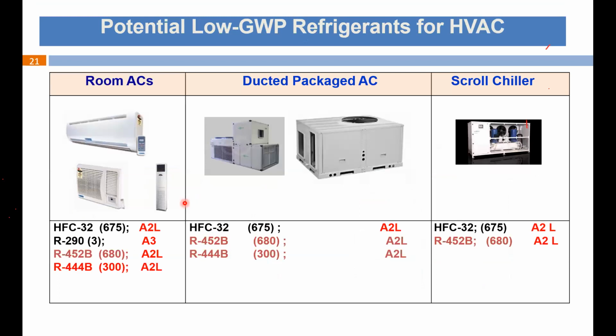Coming to other applications like room AC, R32, R290, R454B, R452B, these are the options available. But if you see, as per the safety standards, they don't comply with the most suitable safety standard, I would say. Though in India also we are using R32 and R290 refrigerants for room aircon, because some manufacturers are using R290, like Godrej and others, but R32 is mostly used. For ductable or package systems, R32 is an option, and again, blends of HFO and HFC refrigerants are an option.